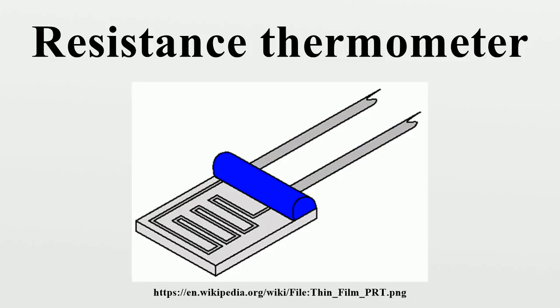Construction. These elements nearly always require insulated leads attached. At temperatures below about 250 degrees Celsius, PVC, silicone rubber or PTFE insulators are used. Above this, glass, fiber or ceramic are used. The measuring point, and usually most of the leads, require a housing or protective sleeve, often made of a metal alloy which is chemically inert to the process being monitored. Selecting and designing protection sheaths can require more care than the actual sensor, as the sheath must withstand chemical or physical attack and provide convenient attachment points.